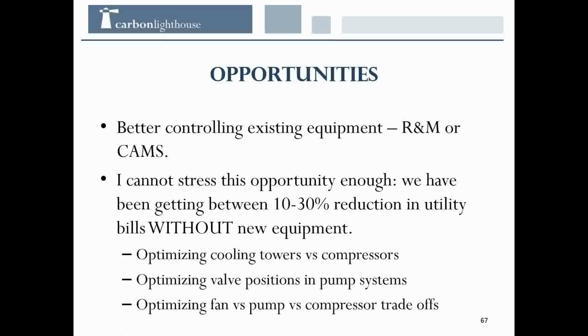So measure actual power, and compare the power use to temperature of water or air, flow of water or air, and outside air conditions. What you want to build up is an efficiency rate for the piece of equipment at every different condition it will experience: when it's cold outside, when it's warm outside, cold outside but warm inside, or vice versa. Then look at the efficiency and overall energy use of all these different pieces of equipment and how they play together. It takes a lot of data, which is why I like data loggers so much, to actually build these different efficiency curves based on load and conditions.